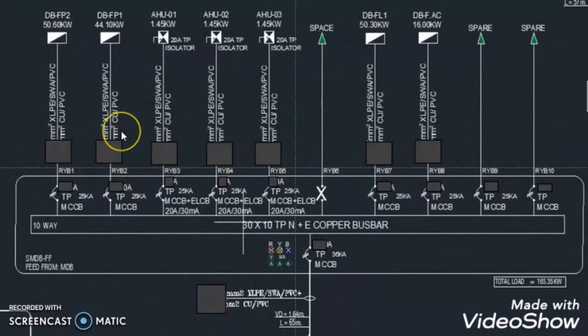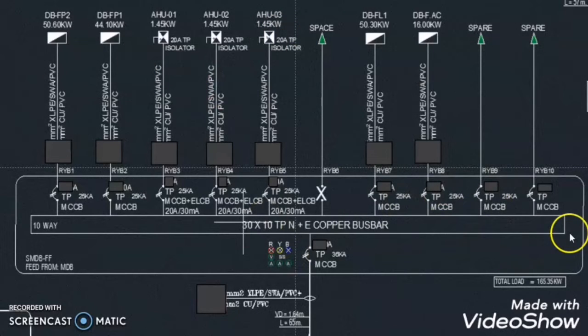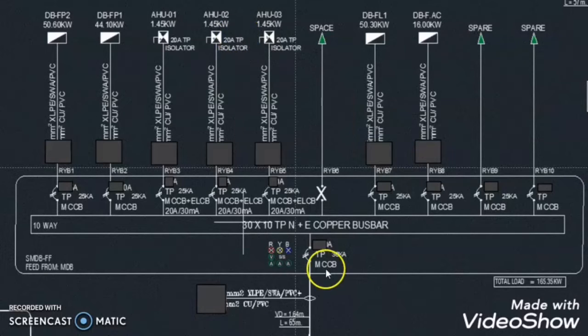There is a difference in ADDC regulation and DEWA regulation for designing the SMDB and LV panel. In DEWA regulation we have to consider the total connected load while calculating or designing the SMDB and MDBs. But in ADDC regulation we have to go for the diversified load in order to design the SMDB and LV panel. However, in both DEWA and ADDC regulation, if we are designing the final distribution board then we have to consider the total connected load.